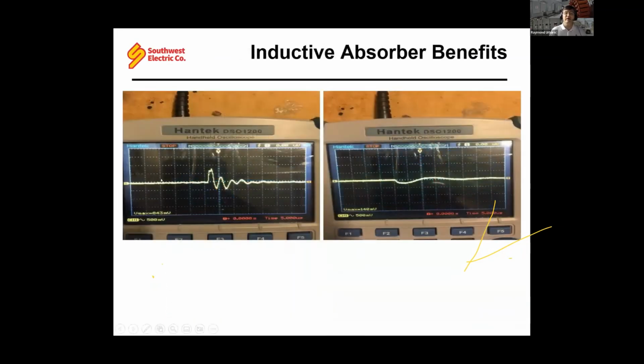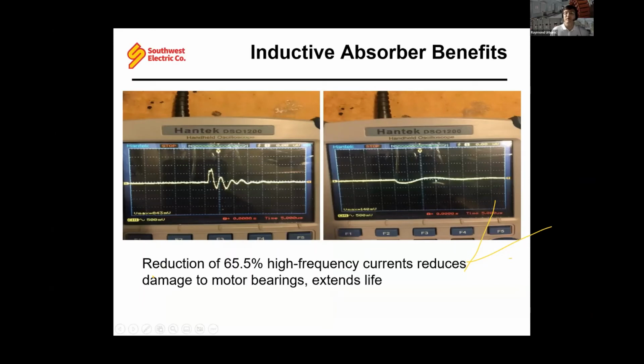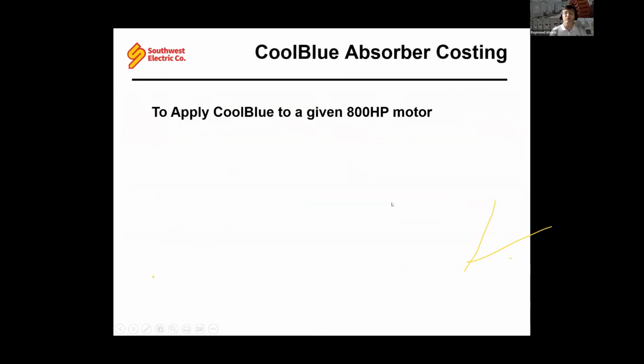And here's a sample of the power quality coming into the motor before the CoolBlue is installed and after. It's not 100% filtering, but it greatly reduces. They say they average about two-thirds of that high frequency current is eliminated after installing these inductance absorbers. And by doing so, you can extend the life of that motor, extend the distance between the required maintenance, and it would pay for itself very quickly.